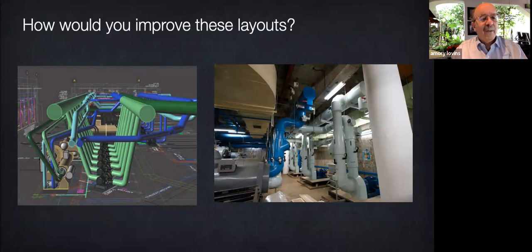The one on the left is kind of interesting. If you rotated those green manifolds a bit, maybe you could run very short diagonals to pumps that are raised up with a catwalk to get to them for maintenance, instead of having all those joints going down and up again. Save a lot of plumbing expense. There's some other stuff you could do there too, although you notice they're pretty good about the long purple connection not having right angle bends. On the other hand, maybe it could run in an arc.